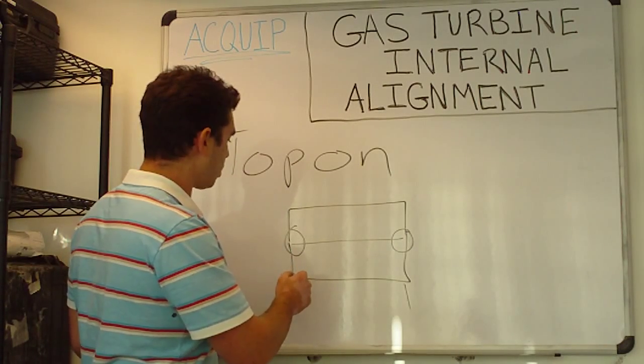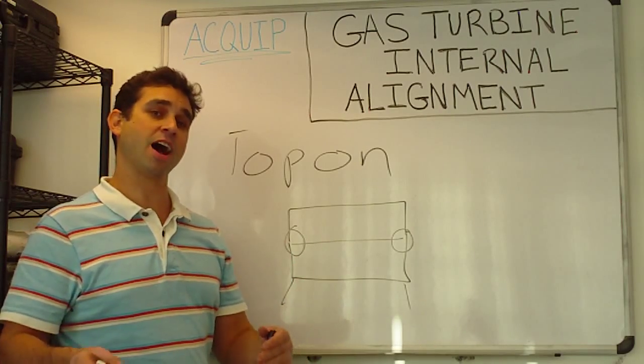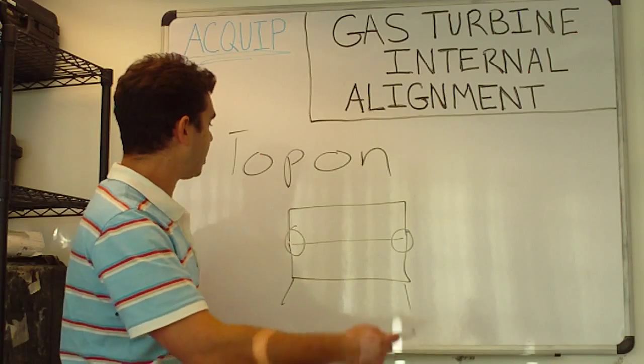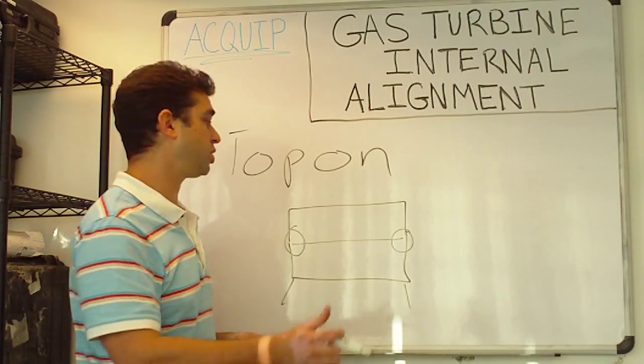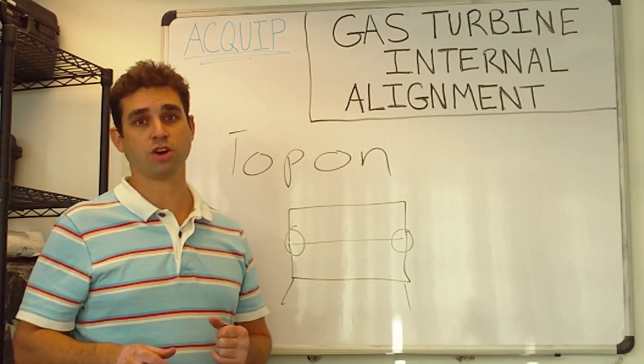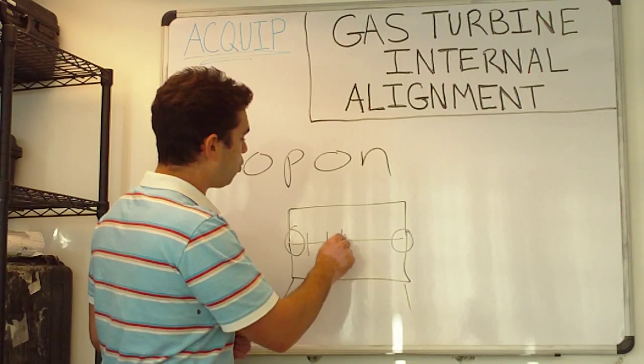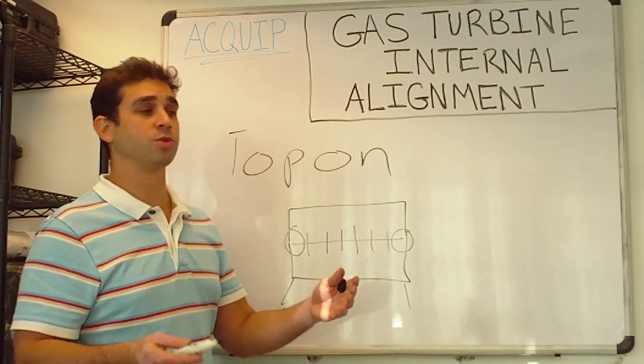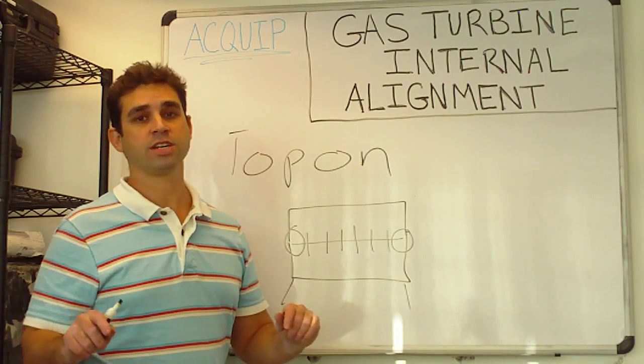So we want to make sure that whether we're doing a frame seven alignment or frame five or a frame six or we're doing a 501 alignment that we have all of the necessary and heavy components bolted back onto the turbine. Now we don't have to have all the bolts back in. What we normally like to do is have every other bolt in and torque down to specification.